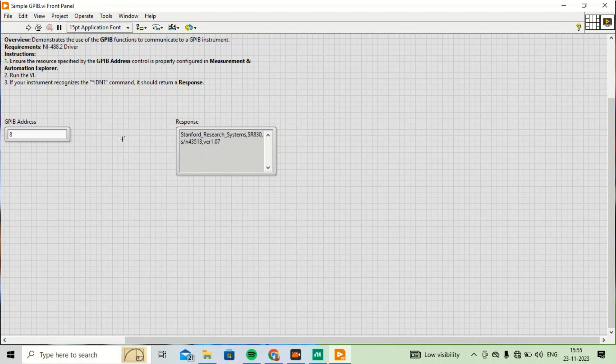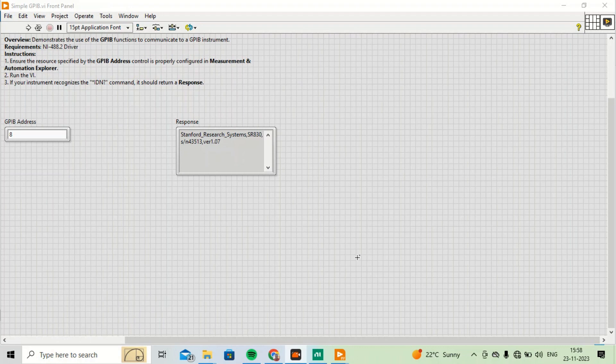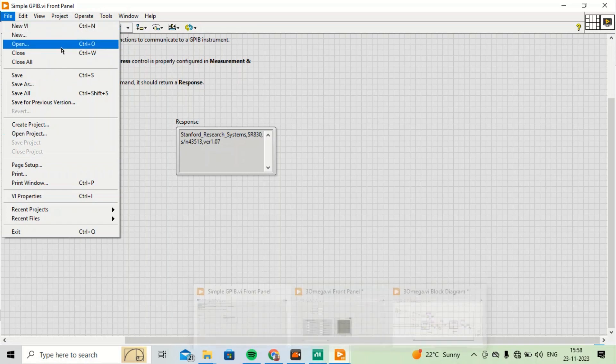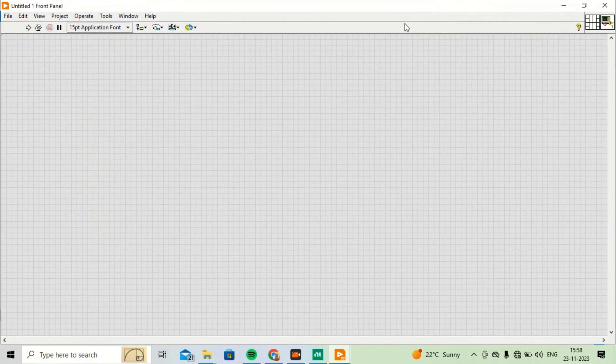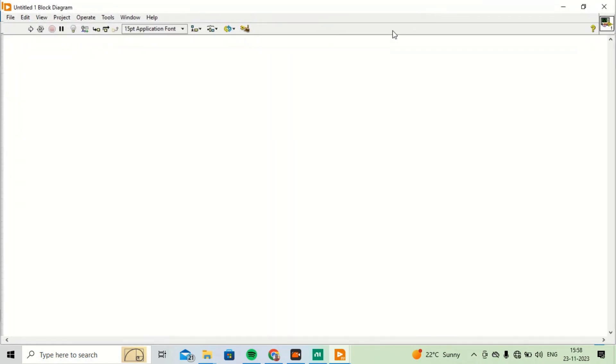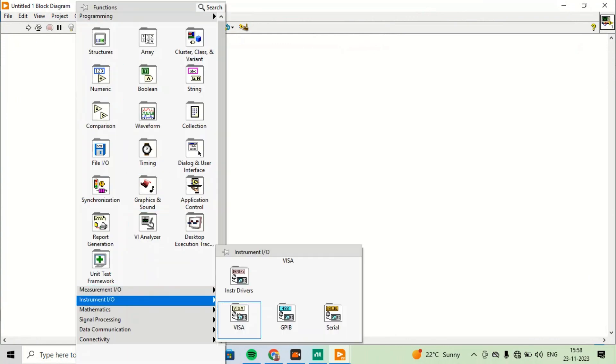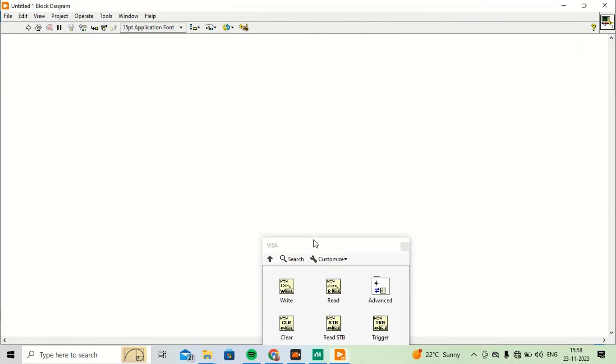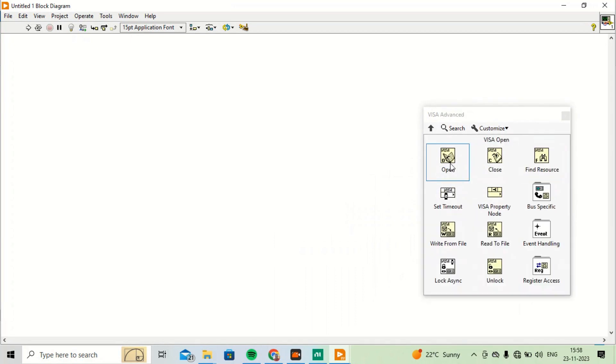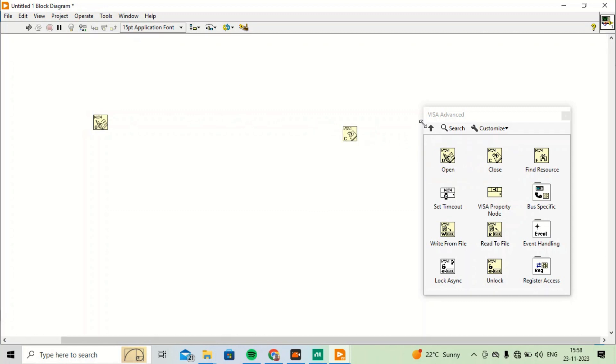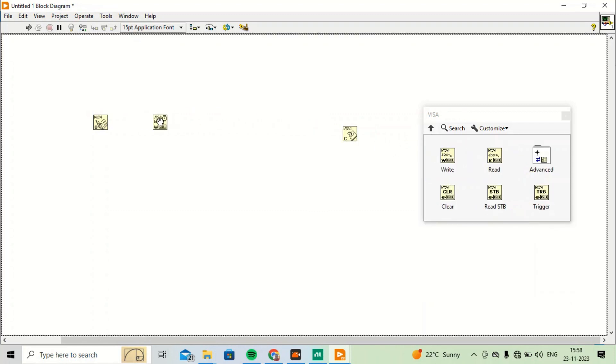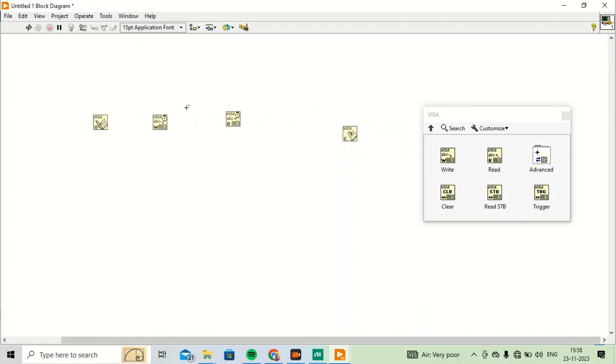It can communicate with the instrument. Now I will make a new VI for communicating with this instrument. I'll go to the block diagram and then I'll put the VISA palette here. First I will have VISA Open, and definitely there has to be VISA Close. Now I will need VISA Write and VISA Read. That's all I need for communicating with any instrument or making a program for any simple instrument.